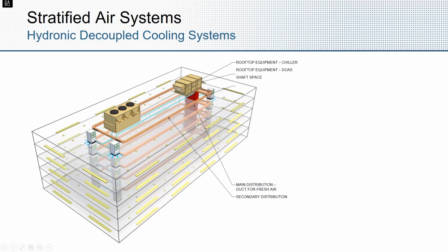There is some leakage through the raised floor air tile system going into the occupied zone, but there are a number of methods to minimize that, especially uncontrolled, undesired leakage through the walls, behind thermostats, and those sort of things. Basically, coordinating and ensuring up front that those are minimized during construction can be done pretty easily to help with that.